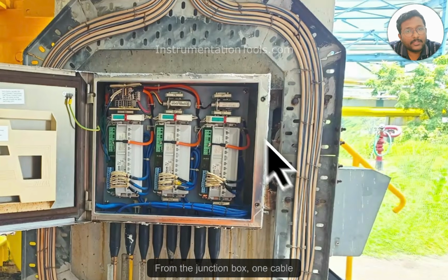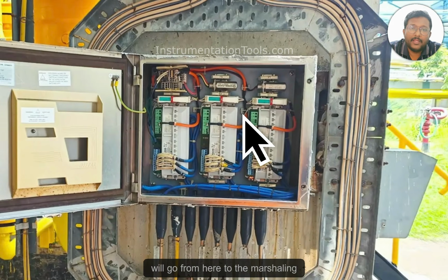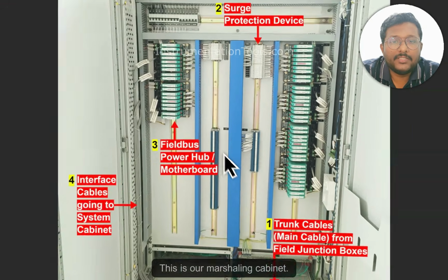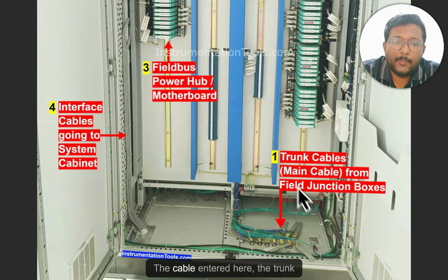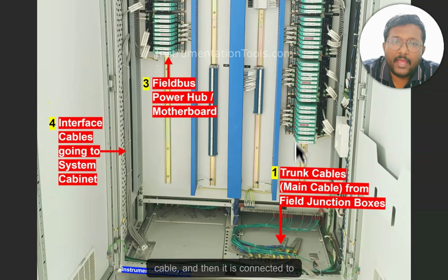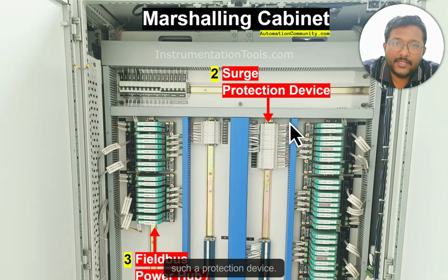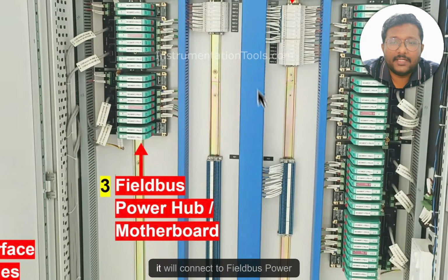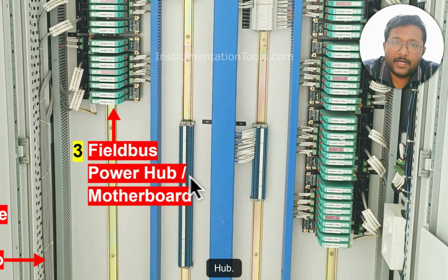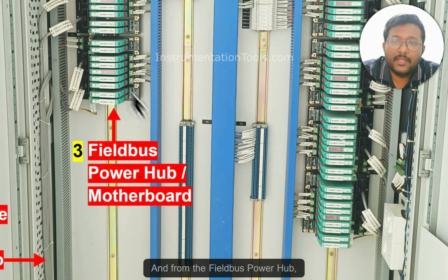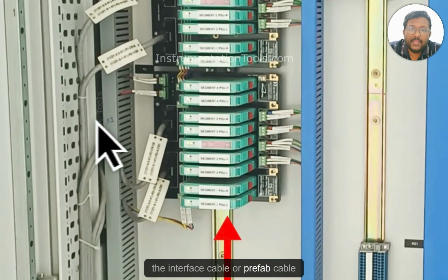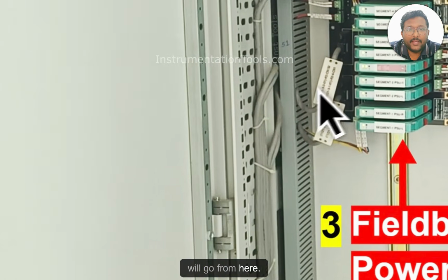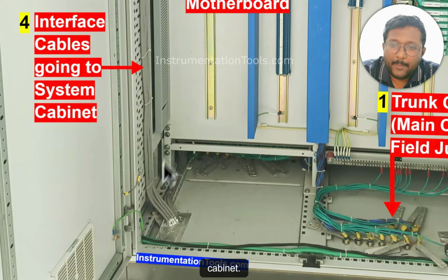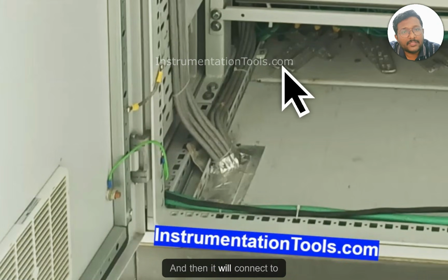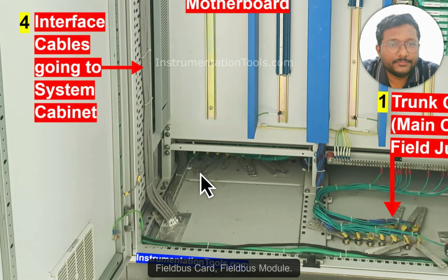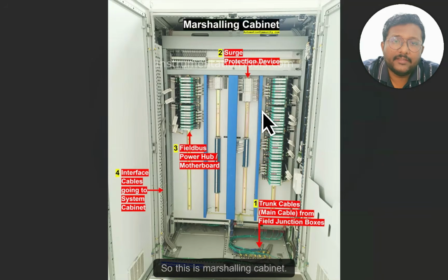From the junction box, one cable will go to the marshalling cabinet, right? So this is our marshalling cabinet. The trunk cable enters here and is connected to the surge protection device. From the surge protection device, it connects to the fieldbus power hub, and from the fieldbus power hub the interface cable or prefab cable will go to the system cabinet, and then connect to the fieldbus card, fieldbus module, right? So this is the marshalling cabinet.